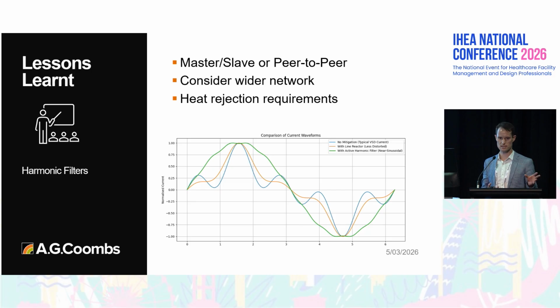It needs to be a master-slave relationship or peer-to-peer. If they're both connected to the same network and you haven't got that arrangement, they're going to see the same distortion and try and inject a corrective current to mitigate it, and you'll lose control and end up with more harmonics than you started with.